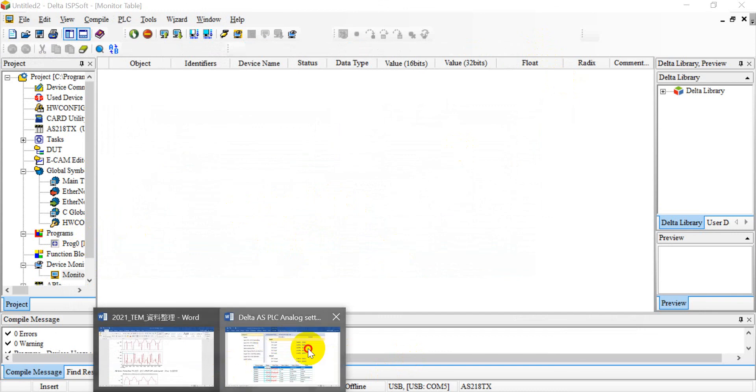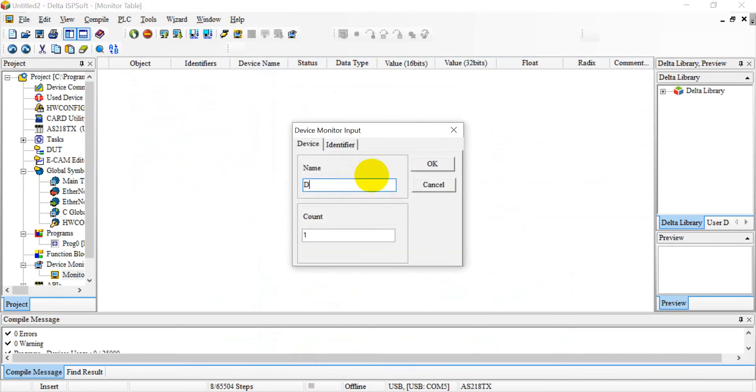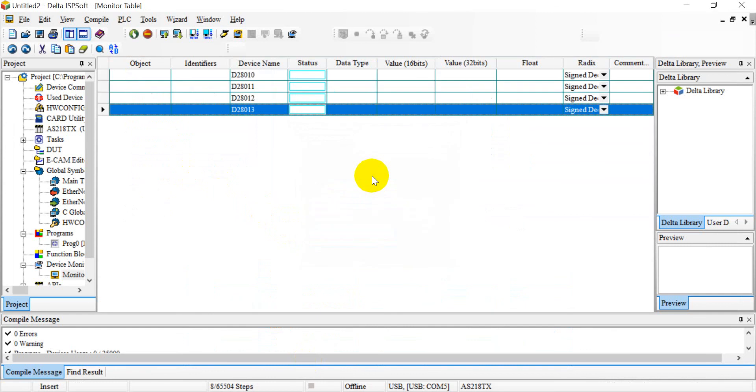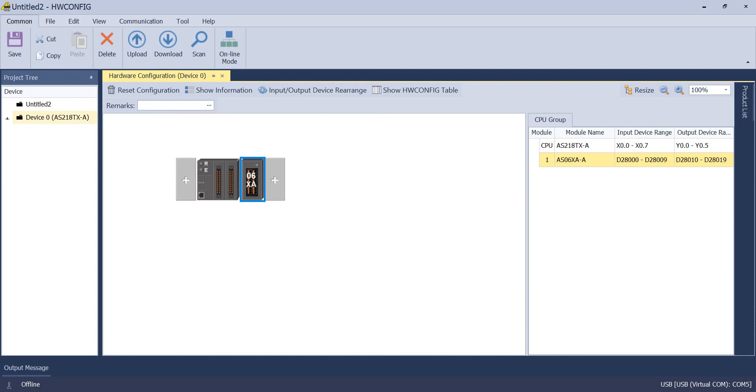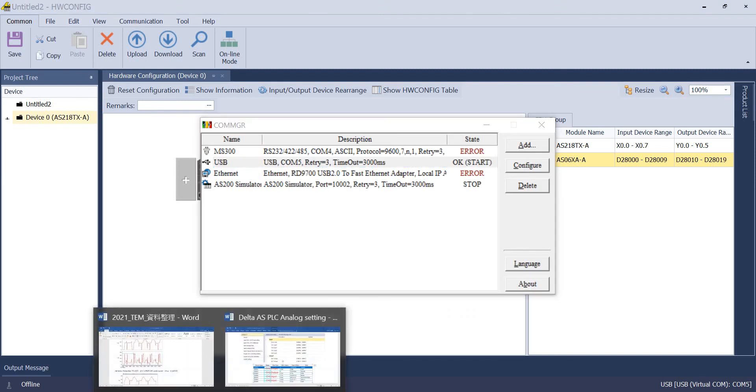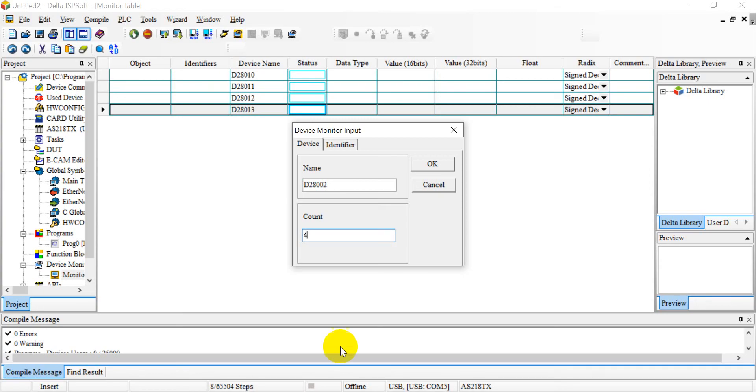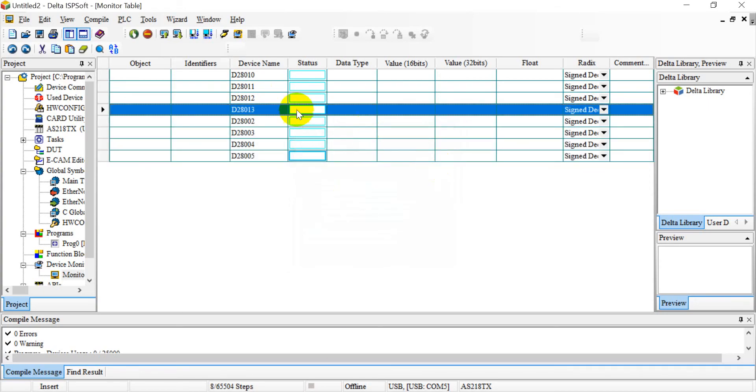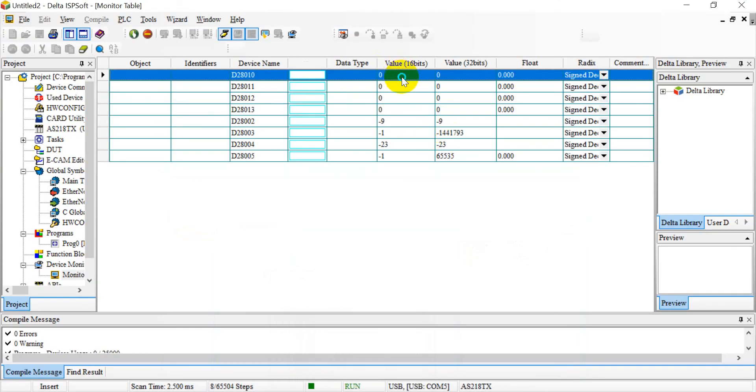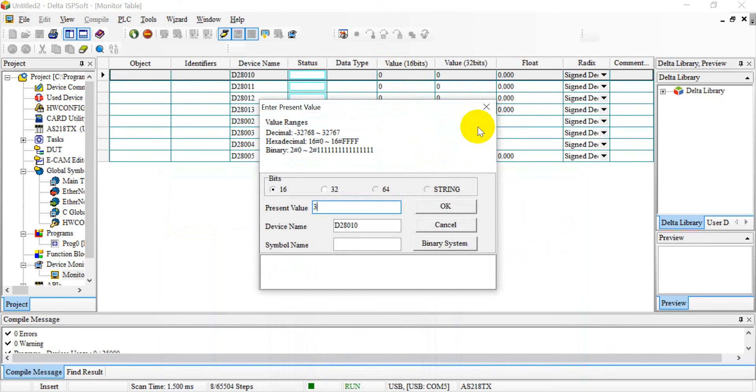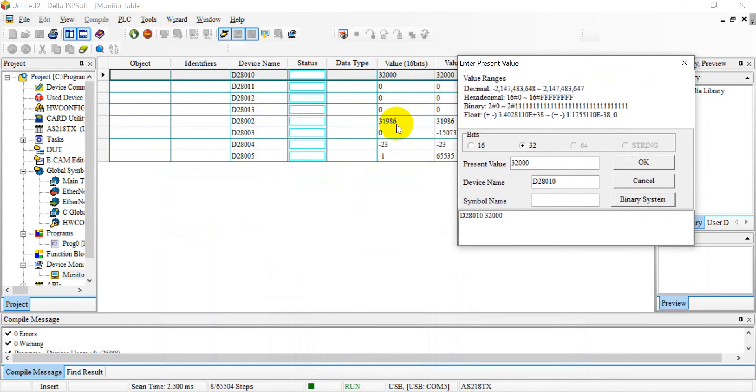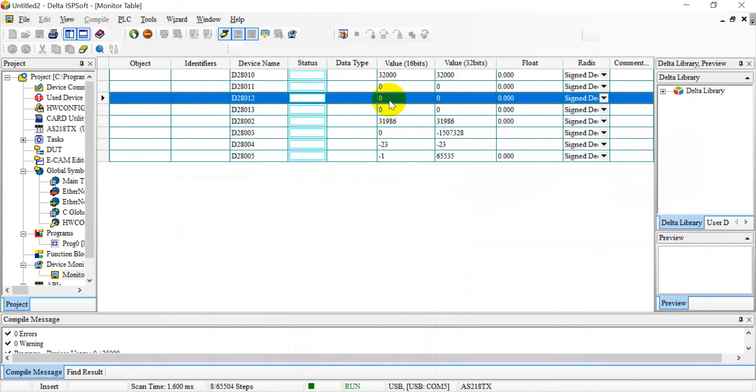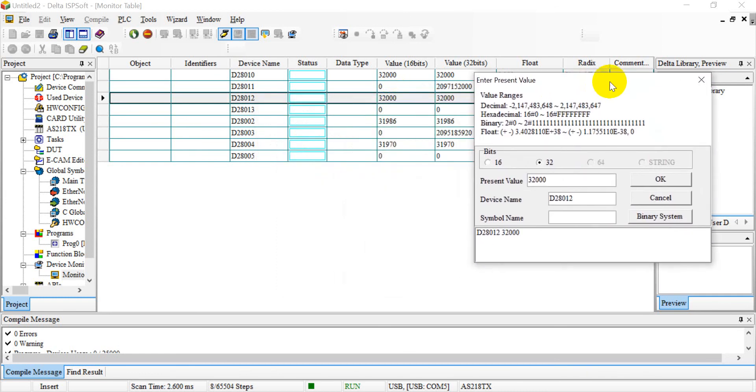Later we can create the device monitor table. If you already forgot, let's go back to check. The output is D28010, this one is for channel 1 and channel 2 output. Then we want to monitor channel 1 and channel 2 input. If you cannot remember we can check again. It will be D28002. Now we use the integer format so we can use 32K. You can see for the input is roughly 32K, which means the maximum value. Then for the current output we also give 32K, so you can see also roughly 32K, which means almost 20 milliamp.